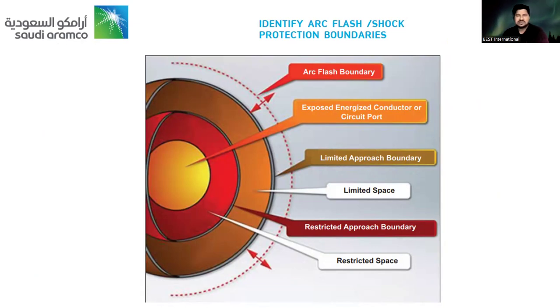There are protection boundaries. It's quite straightforward, self-explanatory. We have the arc flash boundary. Let's start from here: exposed energized conductor or circuit part. We have the limited approach boundary and limited space. Then the restricted approach boundary. No one should go into that area for sure. Restricted space. So bear in mind, without best safety practices related to electrical safety systems, we cannot allow our people to move inside. That's why training and development are reciprocal.